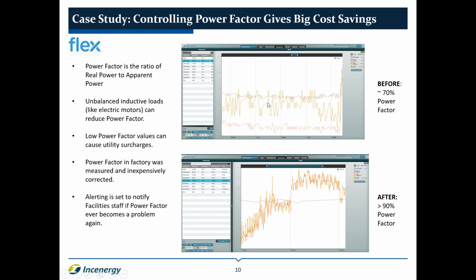It's a fairly simple matter once you've identified where you've got power factor problems to correct them. Things like adding passive capacitance or other power factor correction equipment can be very, very cost effective in relation to the amount of savings you will get on your energy bill. So by using metering effectively and submetering in sections, you are able to identify those areas where power factor is a problem, and you are able to correct them. In this case, we're able to see the power factor has risen to over 90% and eliminated the power factor surcharges for these zones.